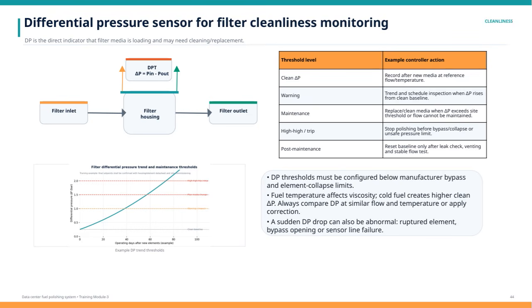If the DP surpasses a set maintenance threshold, meaning the filter is too loaded, we replace or clean the media. At the high or trip level, the system must stop polishing fuel to avoid bypass, filter collapse, or unsafe pressure conditions. It's important to configure these thresholds carefully, staying below manufacturer limits for bypass or element collapse. Temperature also plays a critical role because cold fuel increases viscosity, which raises the clean delta P. So, we must always compare DP readings at similar flow rates and temperatures, or apply corrections if conditions vary. On the flip side, a sudden drop in DP might indicate a problem like a ruptured filter element, an open bypass, or even sensor line failure. After maintenance, the baseline must only be reset once a leak check, proper venting, and stable flow tests confirm that the system is operating correctly again. This structured monitoring ensures that the fuel polishing system runs safely and efficiently with well-maintained filters.